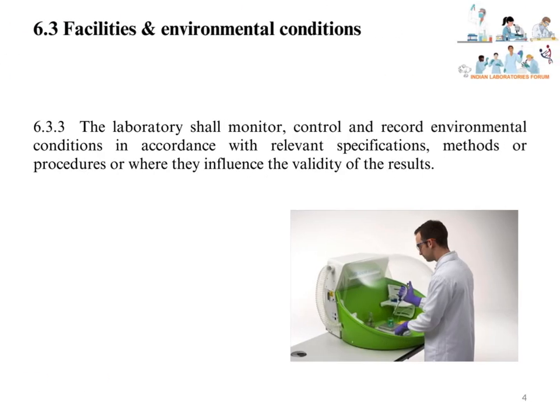The laboratory shall monitor, control, and record environmental conditions in accordance with relevant specifications, methods, or procedures, or where they influence the validity of results. The laboratory has to monitor environmental conditions based on the frequency defined in laboratory-specific procedures and control them — for example, using air conditioners, dehumidifiers, vibration-resistant pads, vibration-resistant tables, etc. Environmental conditions should be recorded per the defined frequency and must comply with relevant specifications, test or calibration methods, or any specific procedure. The laboratory should ensure that environmental conditions are not adversely influencing the validity of results.